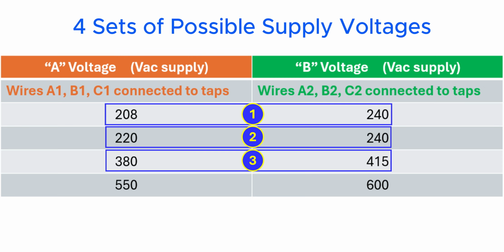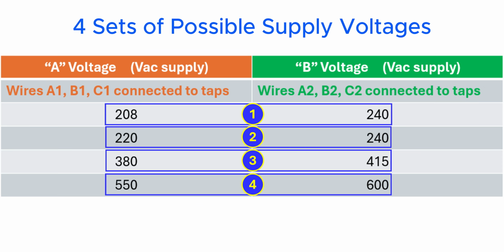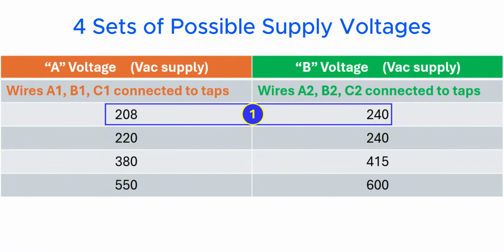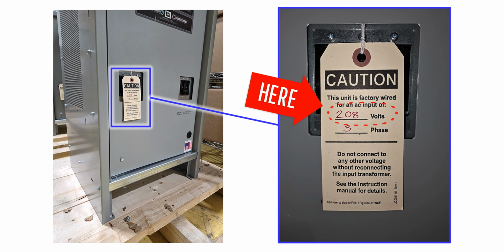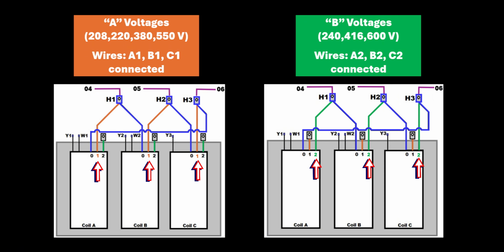There are 4 sets of supply voltages possible for a 3-phase dual voltage ATevo, as shown in this table. Choosing one or the other voltage depends on which coil wires are connected to the primary tap wires. The charger example shown in this video may be wired for either 208 or 240 volt supply voltage. However, the process is the same for the other 3 charger supplies possible. Refer to the caution tag affixed to the AC input circuit breaker to identify the factory set 3-phase AC input voltage for your charger. The process requires switching the wire on each of the 3 coils of the power isolation transformer that connect to the transformer's primary wire taps H1, H2, and H3. Note that these wire taps are connected to the AC input circuit breaker CB1.